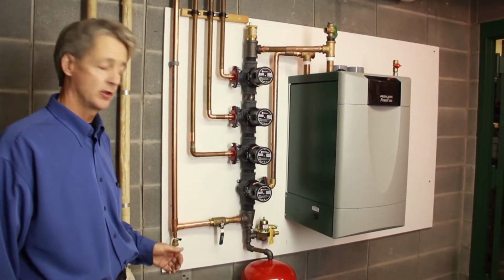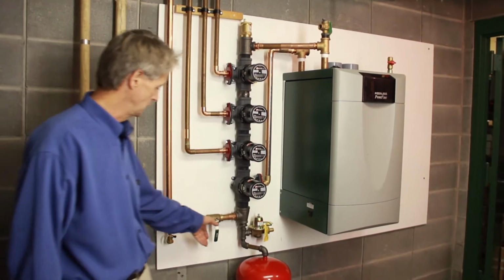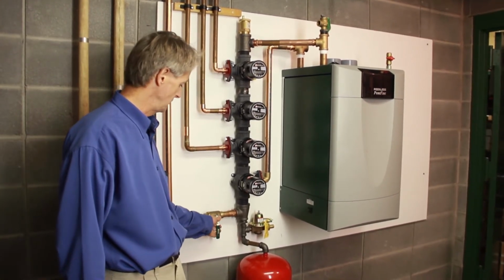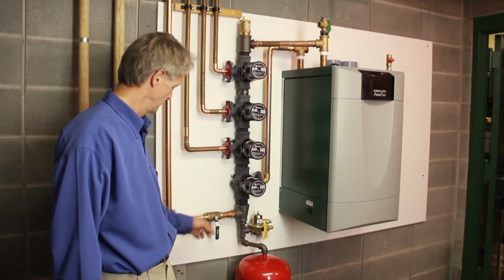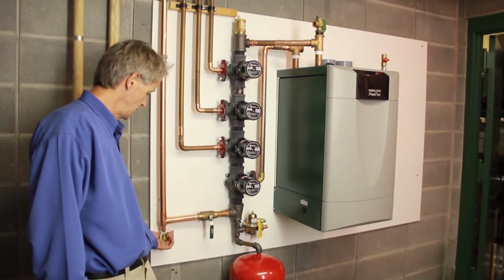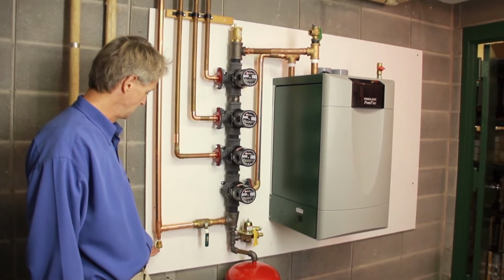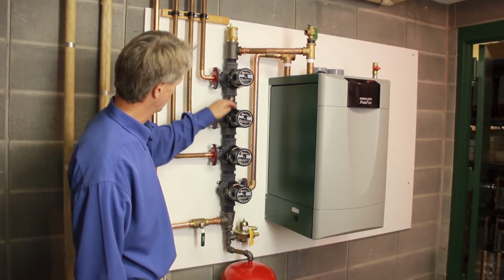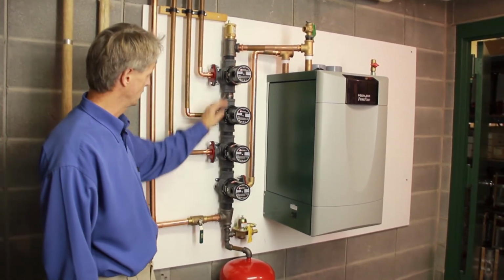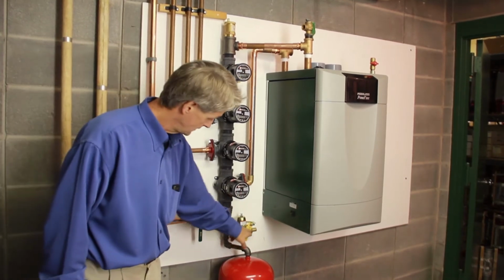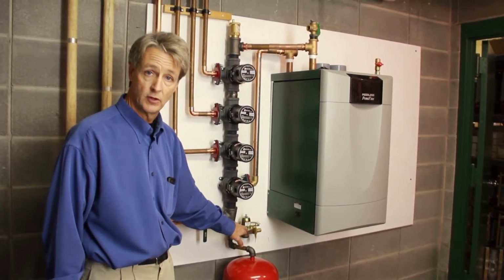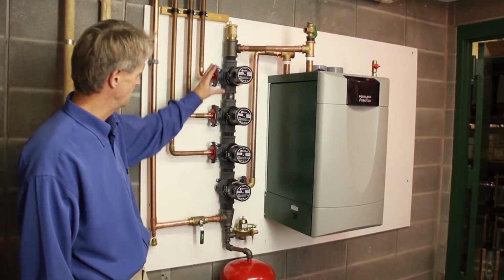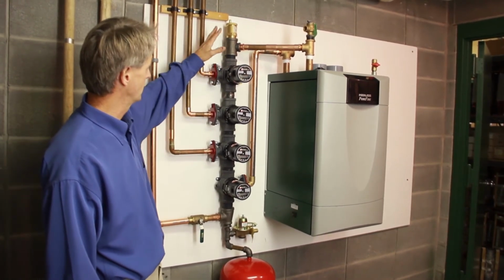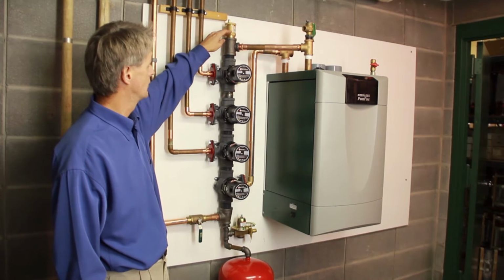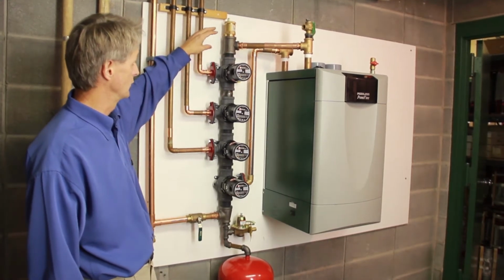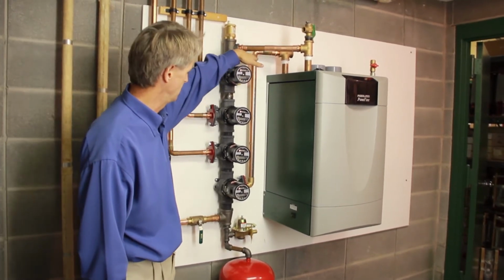In this particular installation, at startup, what we would do is close the common return valve here, open the common drain valve here, hook our hose on the return line, and close all our suction isolation ball valves for these three zone pumps. Then we allow the city water or the fill to come in and pressurize the common pipe. At this point, the highest point in the system is the 1.5-inch vent, so this part of the system becomes fully flooded, with the exception of this high pipe here.